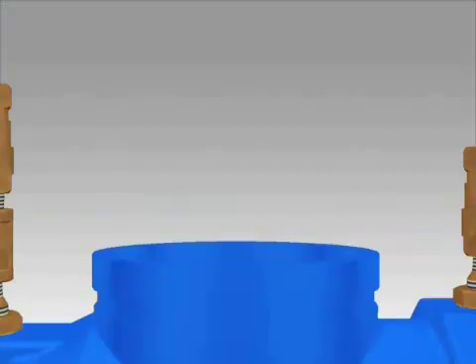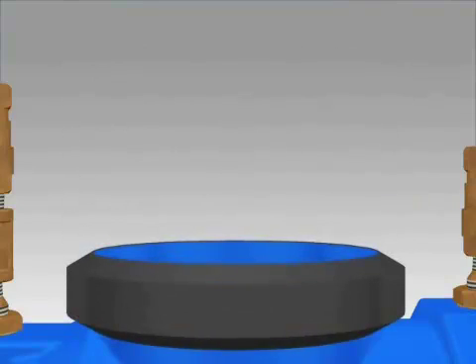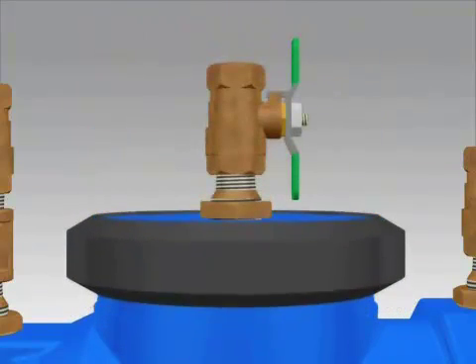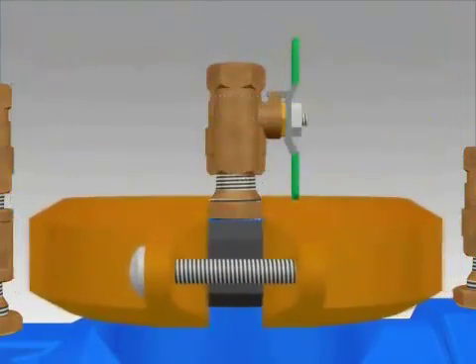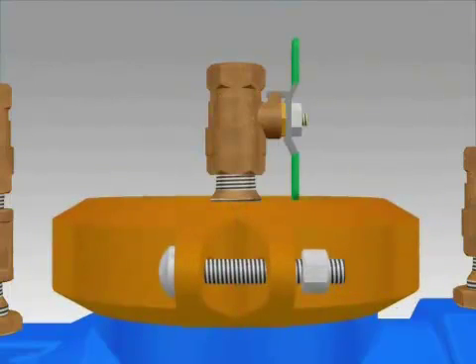Place the groove coupling gasket over the valve opening. Lubricate the outside of the gasket. Replace cover and reassemble groove coupling. Make sure coupling is seated properly and the ends of the coupling halves touch.